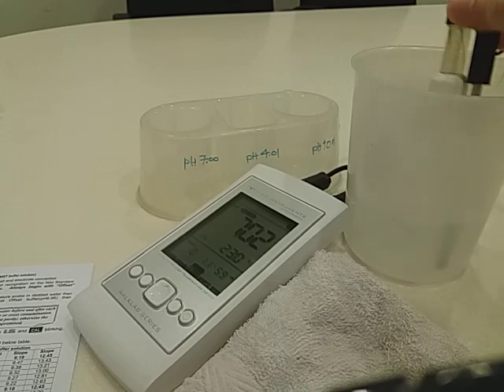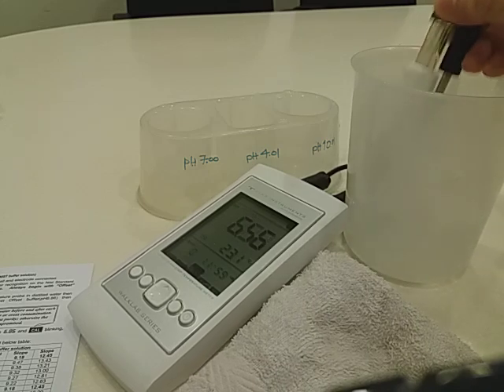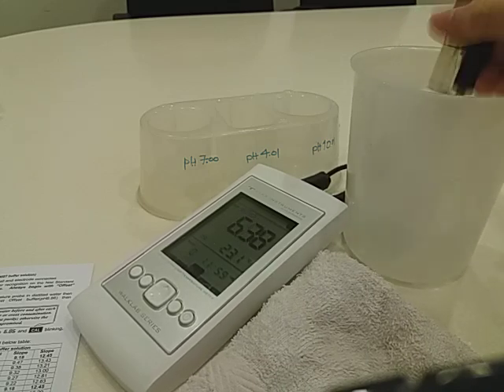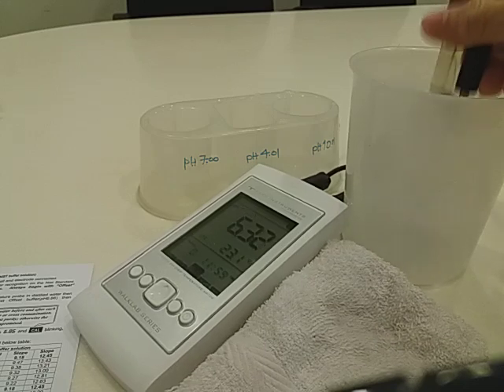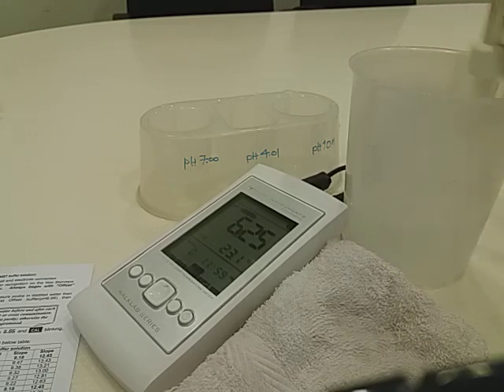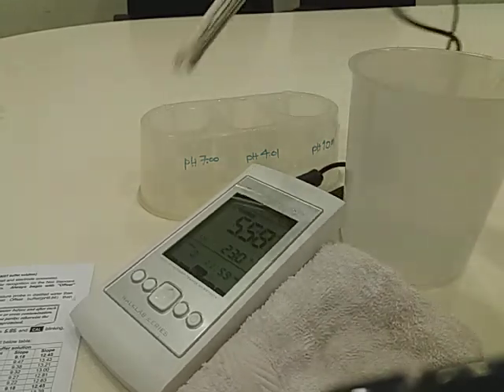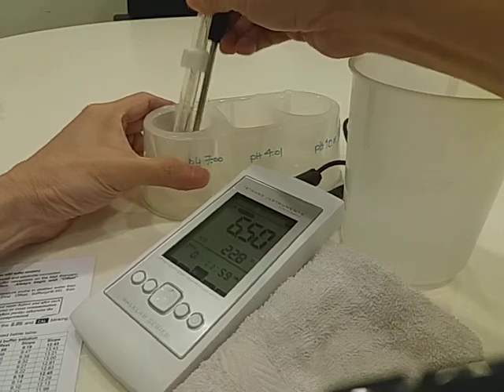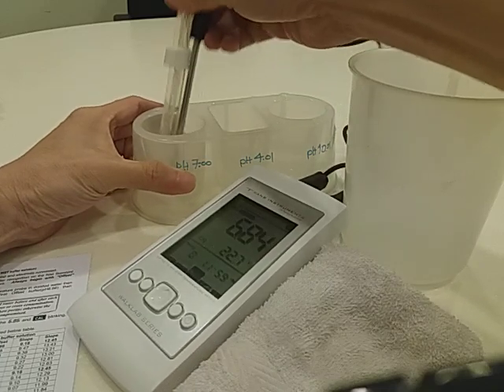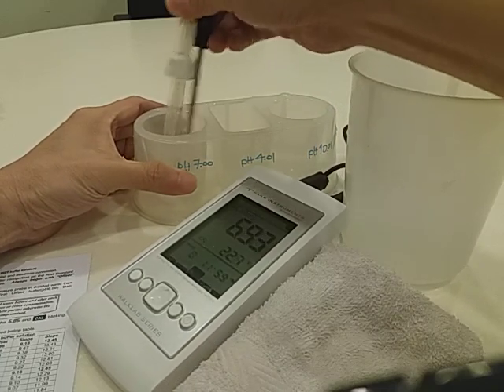First, rinse the pH electrode in distilled water. Make sure you rinse thoroughly, agitate the electrode. Dab dry and dip into pH 7, the first offset point, pH 7 solution.